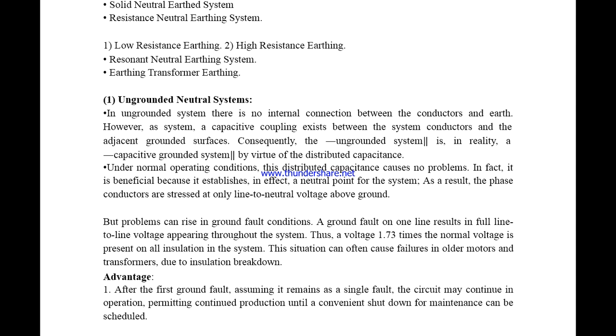But during the fault condition, a ground fault on one line will result in full line-to-line voltage appearing throughout the system. Thus, a voltage of 1.73 times the normal voltage is present on all the insulation in the system. This situation can often cause failures in old motors, transformers, etc., due to insulation breakdown. This is the case in an ungrounded neutral system. Advantages: after the first ground fault, assuming it remains a single fault, the circuit may continue in operation, permitting continued production until a convenient shutdown for maintenance, which can be scheduled.